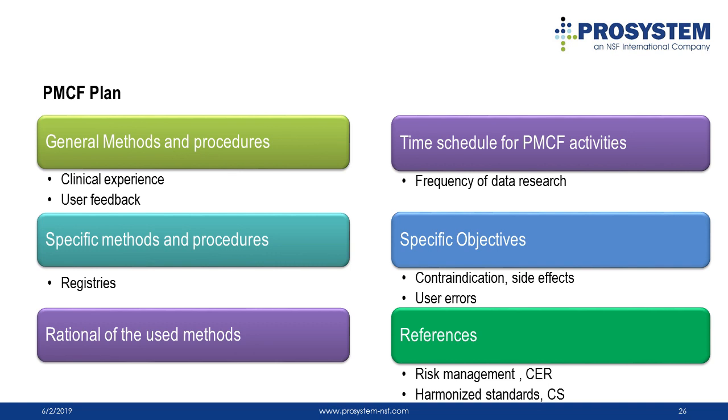Second, the specific methods and procedures of PMCF to be applied, such as evaluation of suitable registers, interviews, or PMCF studies. Third, a rationale for the appropriateness of the methods and procedures used, and also the detailed and adequately justified time schedule for PMCF activities to be undertaken by the manufacturer.